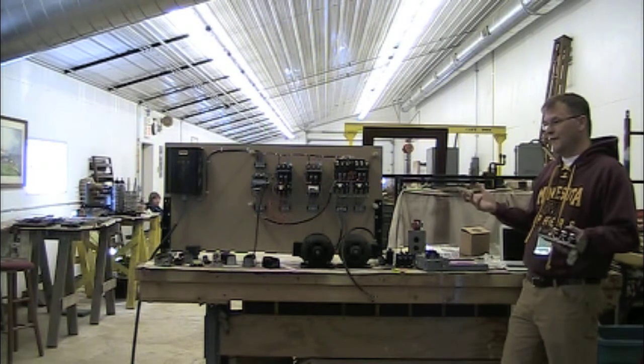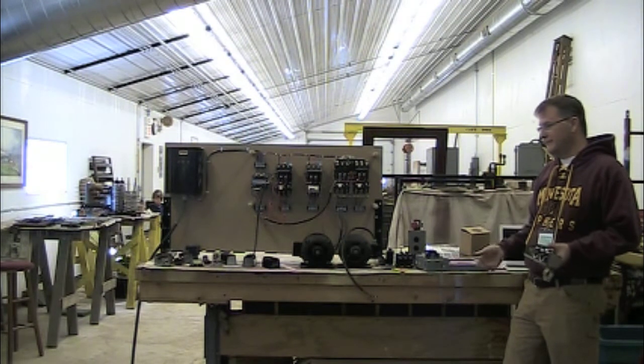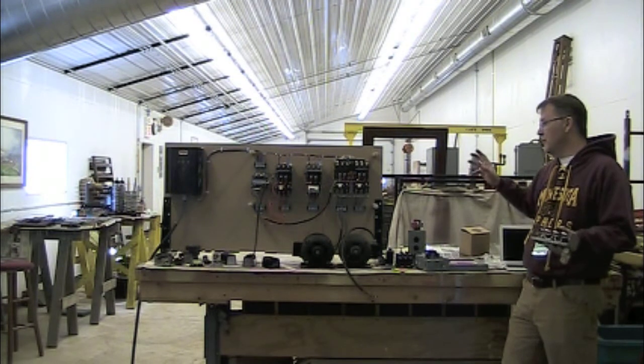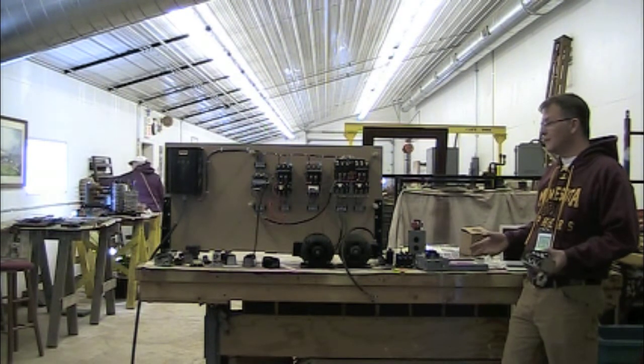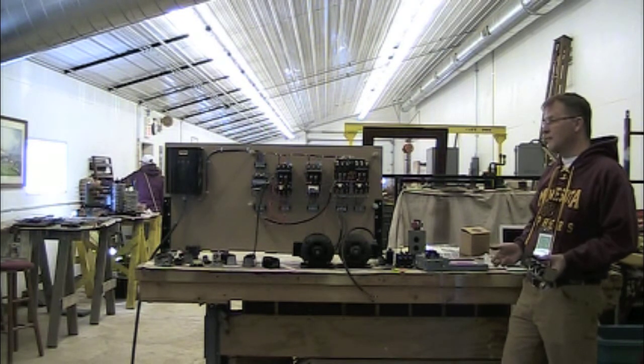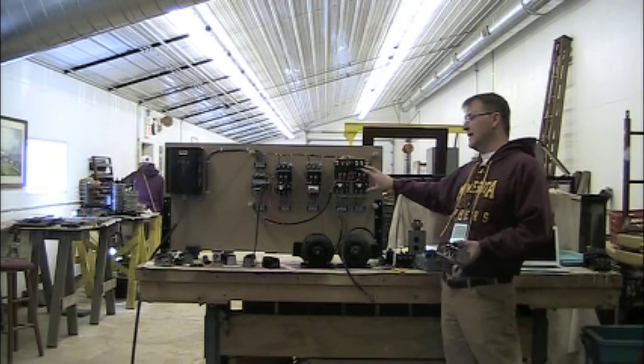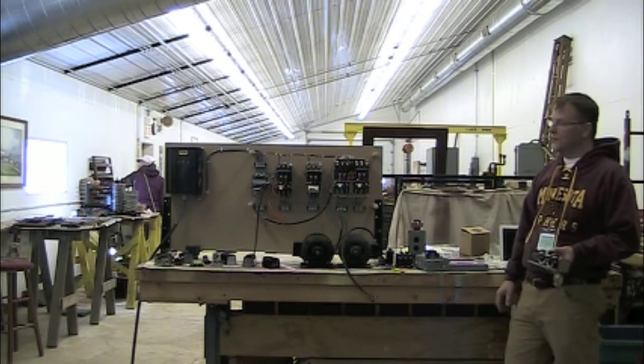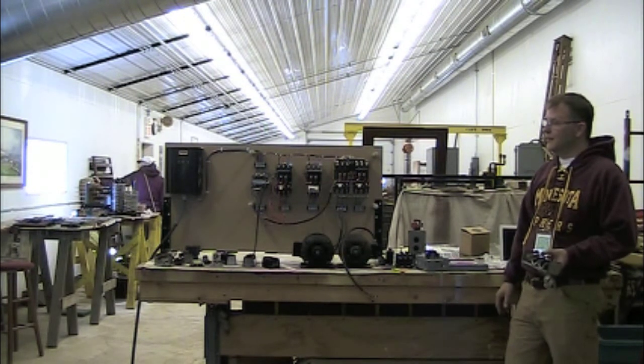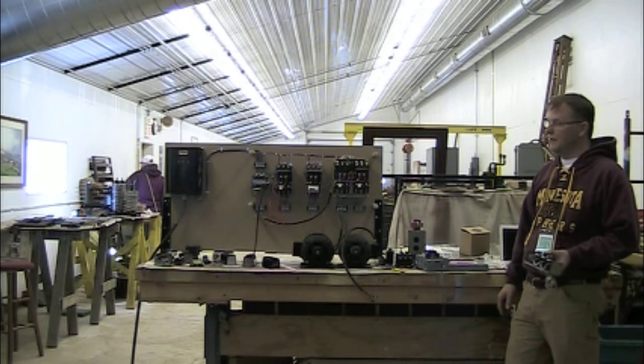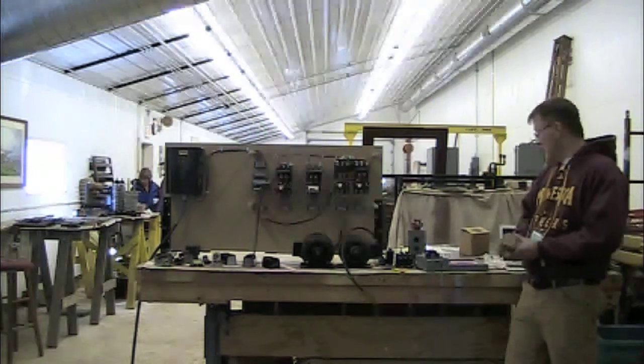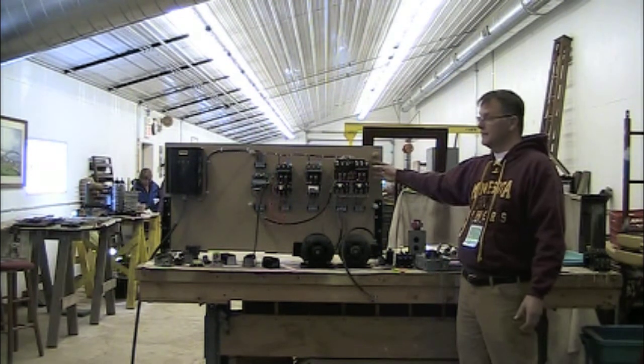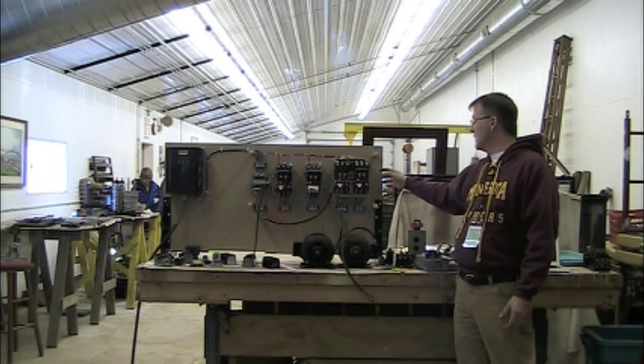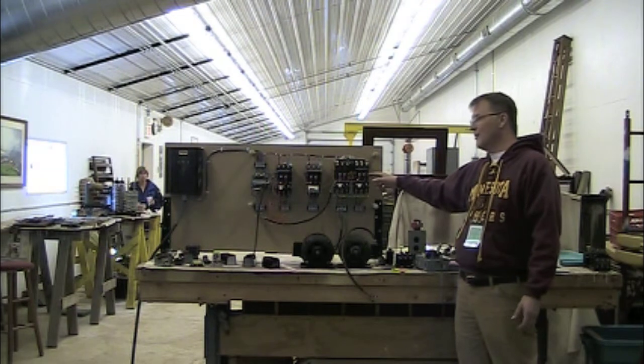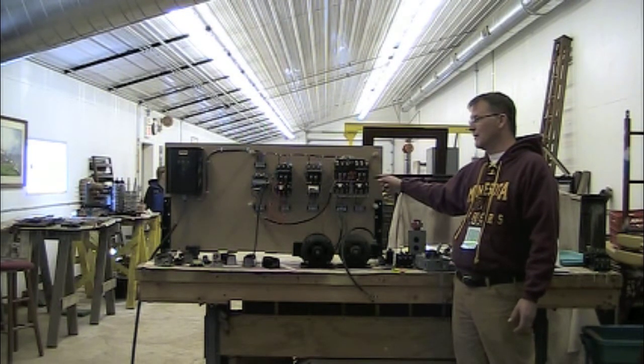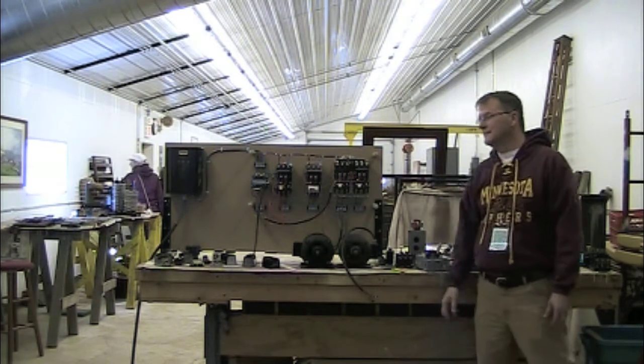You could go, if you really had a consequent pole type multi-speed motor and needed it, you could build all the logic and you could do all the interlocking electrically and successfully run the motor. You could, with the right sets of contactors, do that logic to do the rewiring, and do it based on looking at the wiring diagrams of how a consequent pole starter is set up. It's complicated, but. And then you can also buy, they make adder poles for these. So there's things that go on the sides of these. And you have to be careful then, because the coils are rated for the number of poles. So if you add too many poles, it needs a different coil to be able to close the adder deck on it.